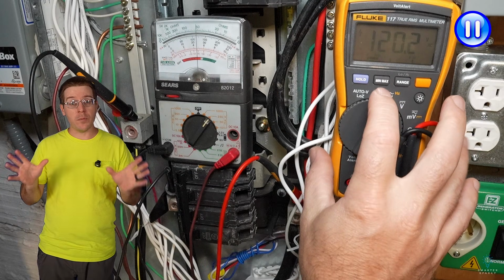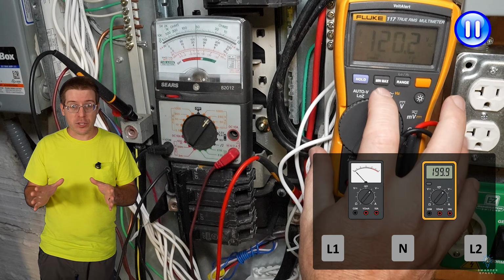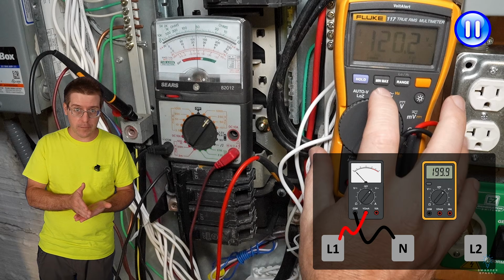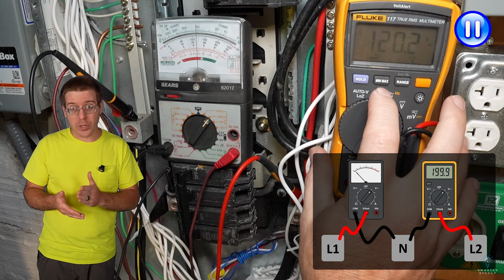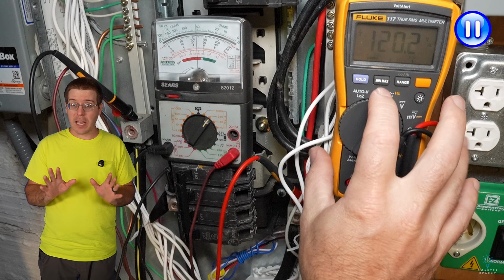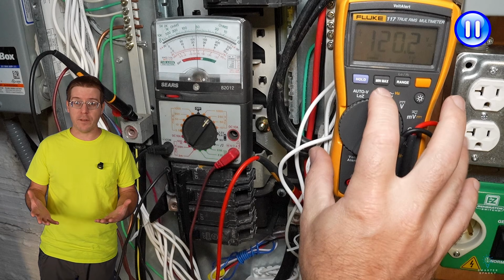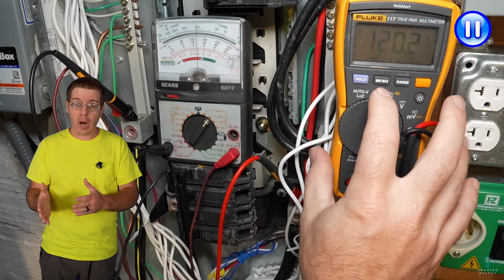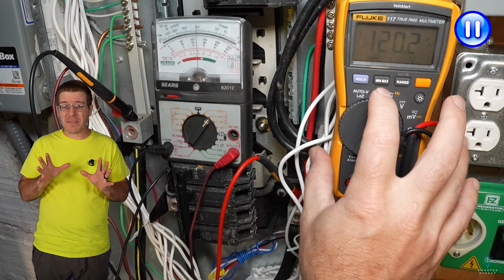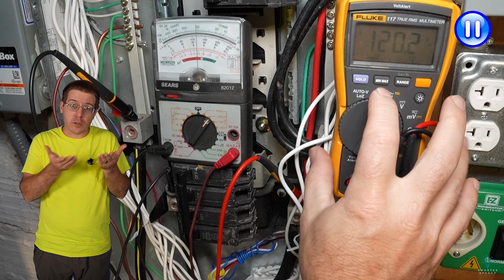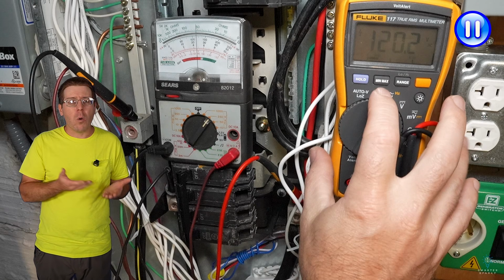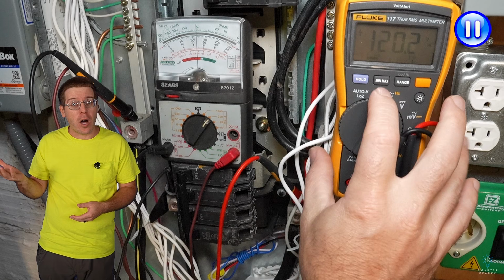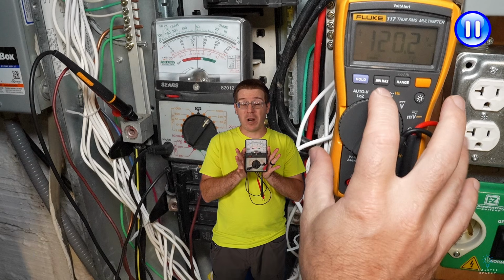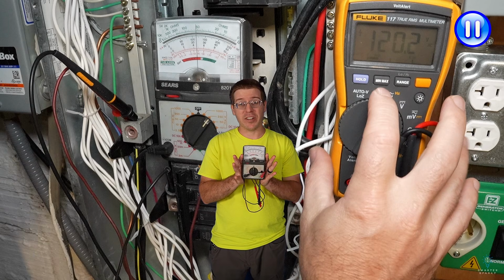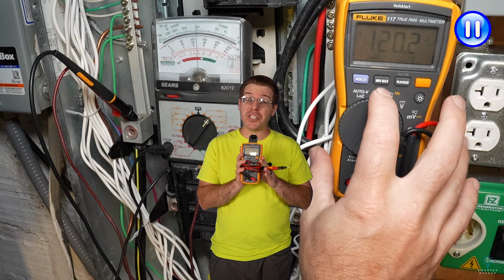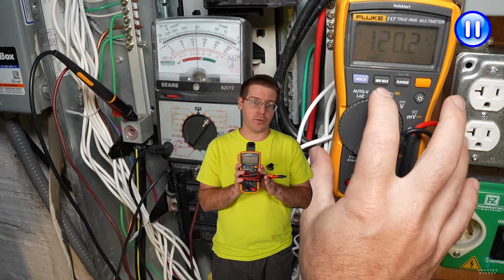What I did here was set up 2 meters side by side. The analog meter is measuring the voltage from line 1 to neutral, and the digital meter is measuring from line 2 to neutral. This isn't a necessary step in the troubleshooting process. We've already got enough information from just using 1 meter that the problem is upstream from this panel. The purpose of this setup is just to illustrate that when we see a voltage drop on one line to neutral, we're gonna see a voltage increase on the other line relative to neutral. Additionally, I wanted to show that a fancy meter is not necessary to see these concepts. But I do switch to 2 digital multimeters later on in the troubleshooting process.